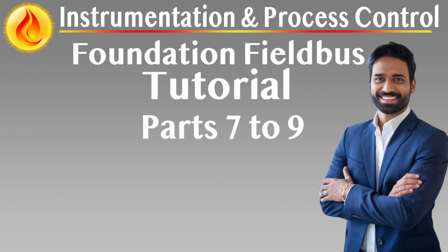The HSE network forms the plant-wide Fieldbus backbone and interconnects various system components including host systems, DCS, PLC, Fieldbus interface modules, FIMs, remote I/O subsystems, engineering workstations, asset management systems, AMS, and HSE-compatible field devices. One of the core advantages of HSE is its ability to aggregate and route data between multiple H1 segments through linking devices like the Fieldbus Linking Device, FLD, or FEM.